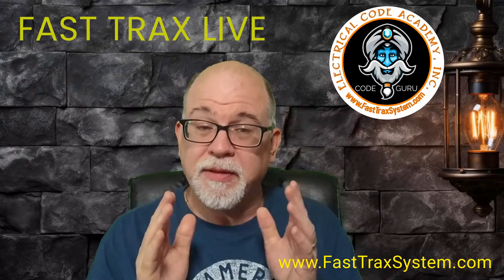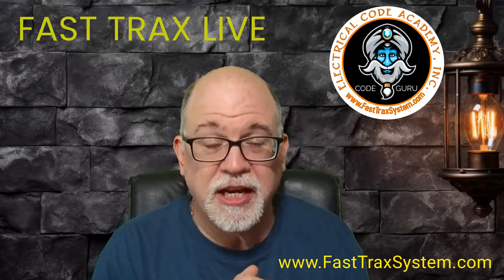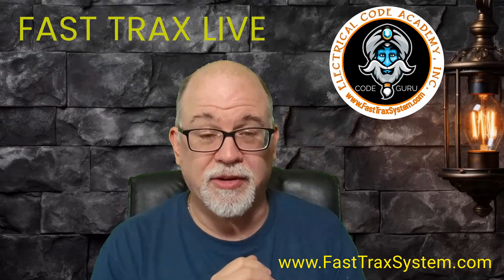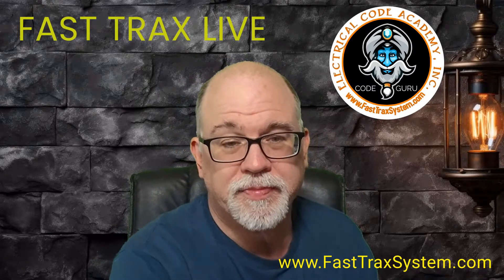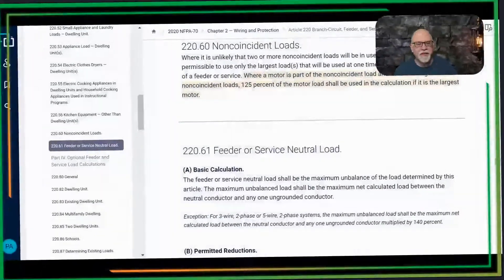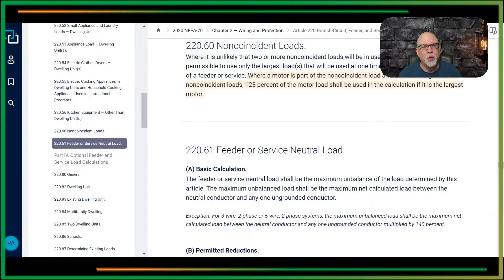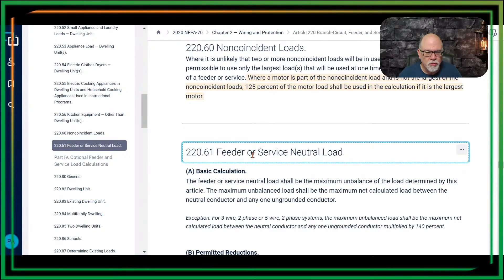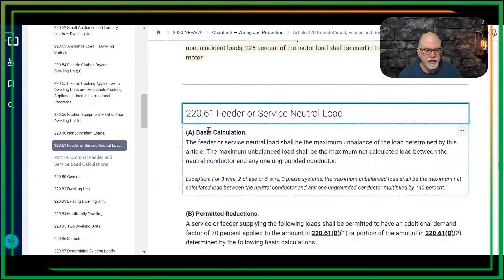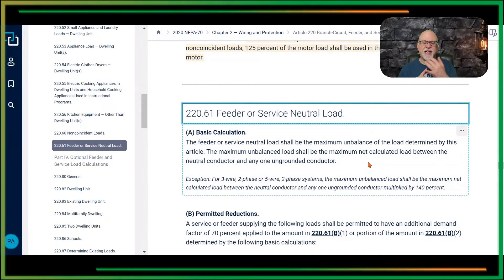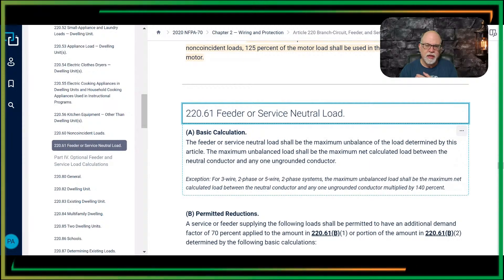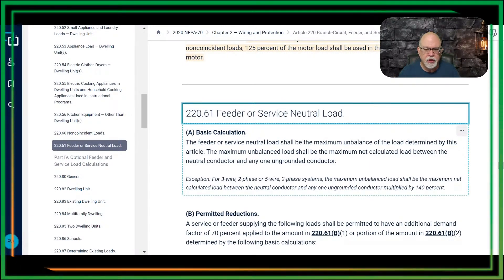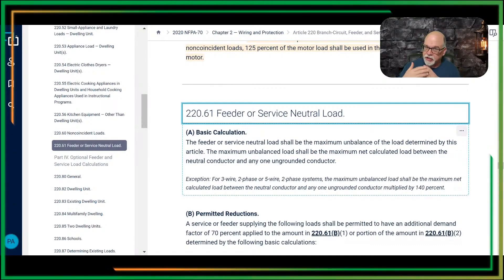What's the change I'm talking about that you need to be aware of? It really is a change of one word, and it makes a significant impact on how it's applied in the code. So let's go look at it. This is the 2020 edition of the NEC. When we're talking about a calculation, we're talking about the feeder or service neutral load — basic calculation. All we're trying to do is size that feeder or service neutral load to the maximum unbalanced load determined by Article 220.